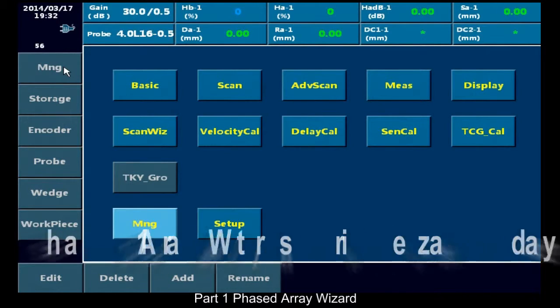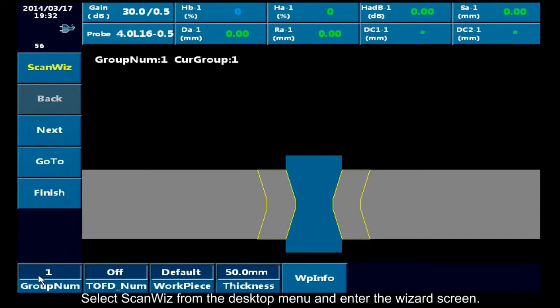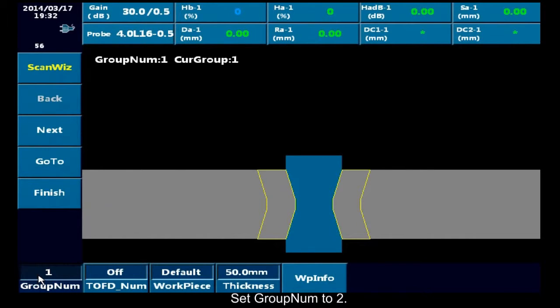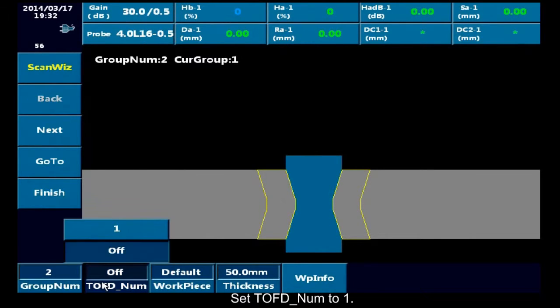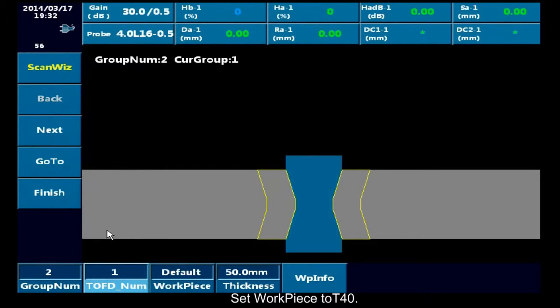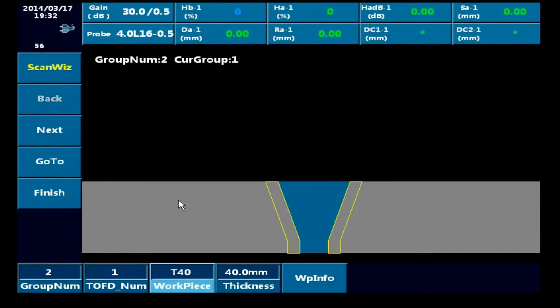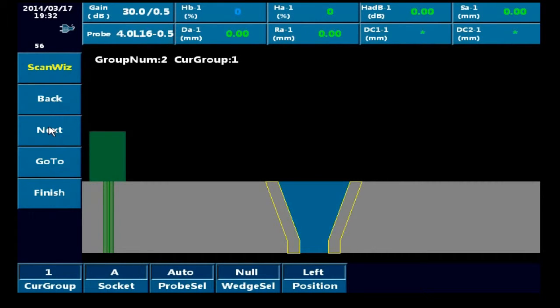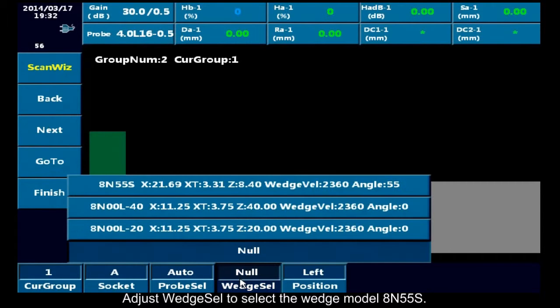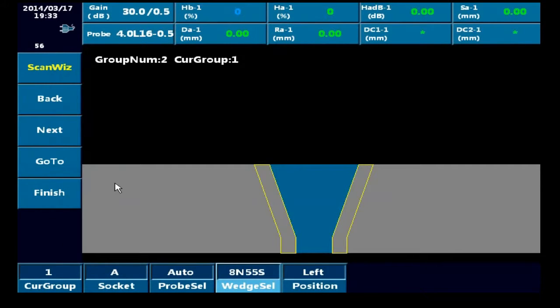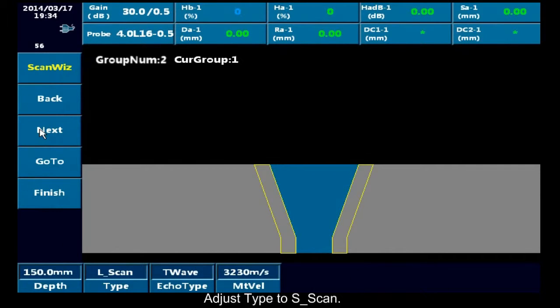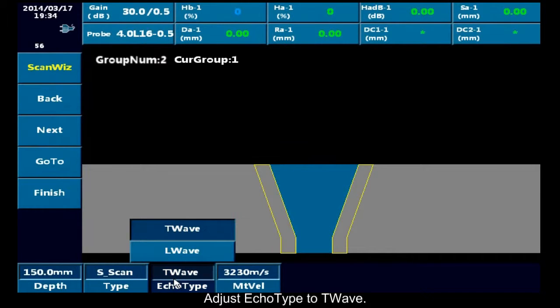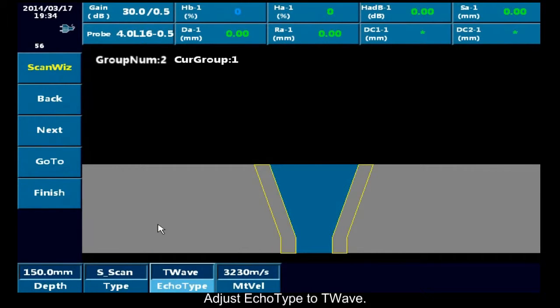Step 2. Scan Wizard. Part 1. Phase Array Wizard. Select Scan Wizard from the desktop menu and enter the wizard screen. Set group number to 2. Set TOFD number to 1. Set workpiece to T40. Press Next. Adjust wedge selection to select the wedge model AN55S. Click Next. Adjust type to S-scan. Adjust echo type to T-wave. Press Next.